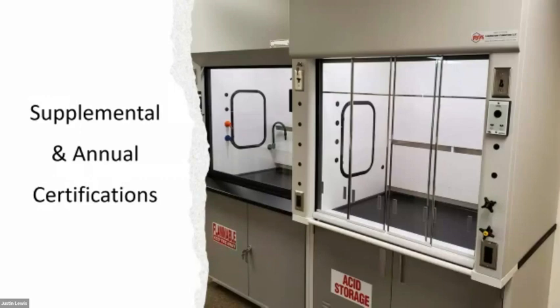Then we have supplemental and annual certifications. Now, even though a project comes to a conclusion, often there are opportunities for ongoing commissioning and TAB scope. If this is a lab or a healthcare facility, do they need regular room certifications and hood certifications? Is this a clean room? Do they need pressure cascades certified every year, or sometimes more than that? If it's a facility with dust collection or tools, you may need to set airflow through the dust collection system or the acid exhaust as tools are moved and adjusted.